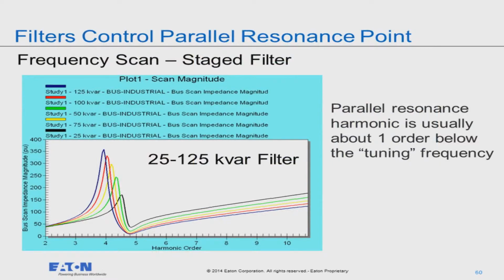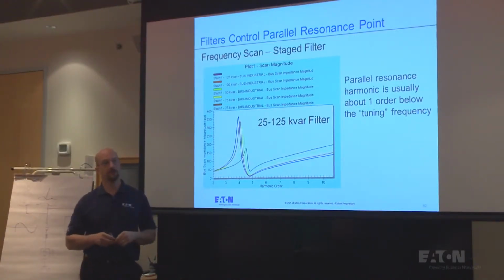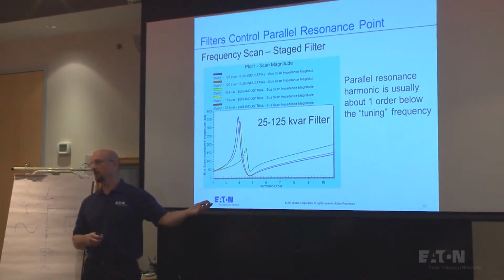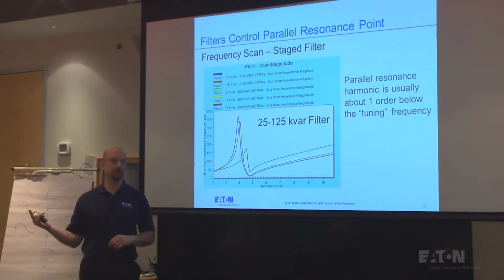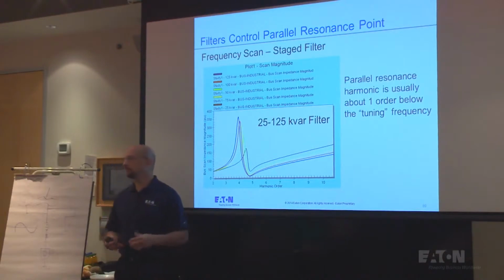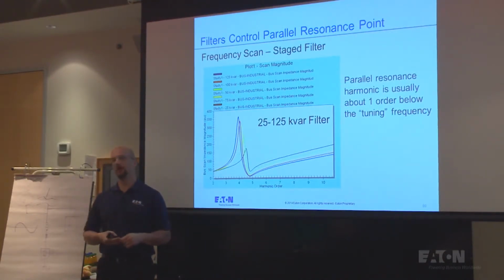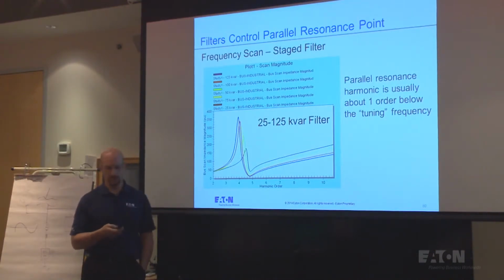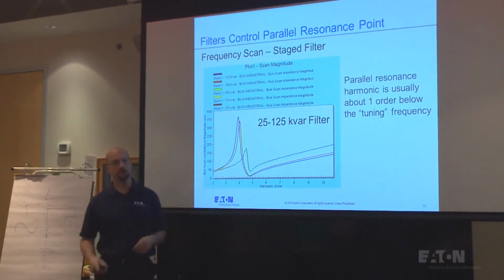What's the downside of putting a really big capacitive filter, which is basically a capacitor and reactor? What's the downside of putting this huge monster filter on there? If I put too much capacitance on, I'm going to go leading power factor. What doesn't like leading power factor? Generators don't like it, right? The other thing is, if I put too much capacitance, I build up the voltage. And if my voltage gets too high, now I start to have other issues, like the DC bus on the drive doesn't like that. Might trip on over voltage. So you have other issues, and you try to match this, and that's why usually they're switched in steps.